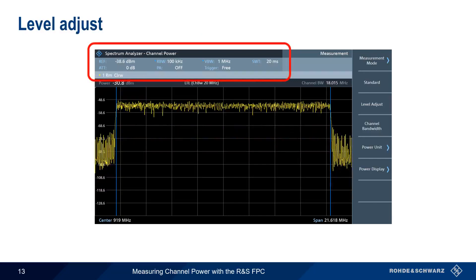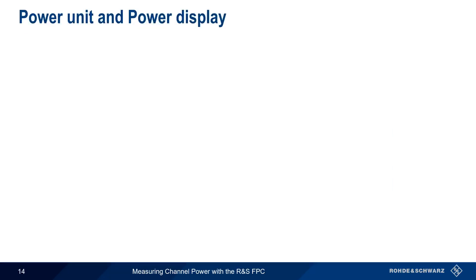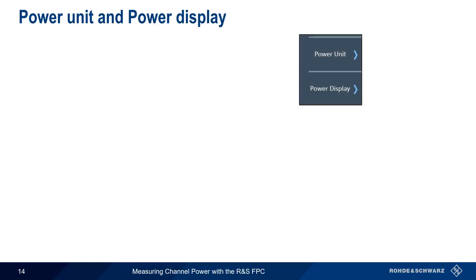Although we can manually set the span, resolution bandwidth, reference level, etc., the Level Adjust button will automatically optimize settings for the chosen channel bandwidth. Power Unit and Power Display can be used to change how we view the measured channel power results.